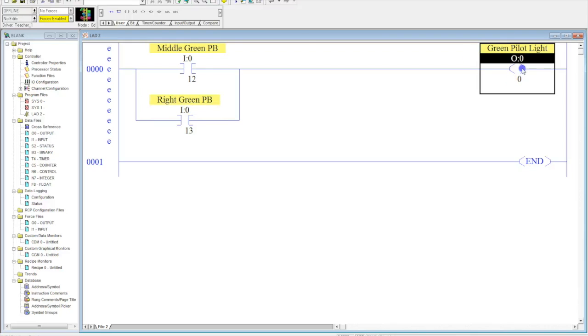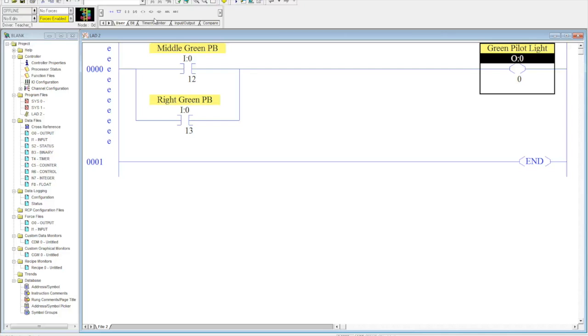Now, this is something in my class that I don't encourage students to do very often. The only time I encourage outputs to be put in parallel is when it's a pilot light that is on a control panel that is meant to be activated only when the output that it represents is activated. That's the only time I ever do it. But, I want to show you guys how to do it because it's an important skill to know.